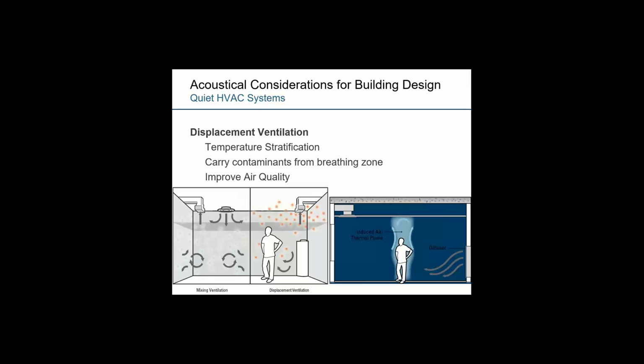Another type of HVAC system I wanted to mention with respect to quiet nature is displacement ventilation. Displacement ventilation is a little bit different from a traditional mixing overhead VAV system in that air is typically introduced at lower velocities closer to the occupant, and because of that, it can have a number of benefits. For one, it can improve the overall air quality of a space, but it also has very low discharge sound levels because of the velocity and the temperature of air being introduced in this manner.